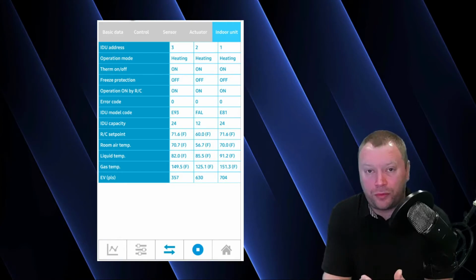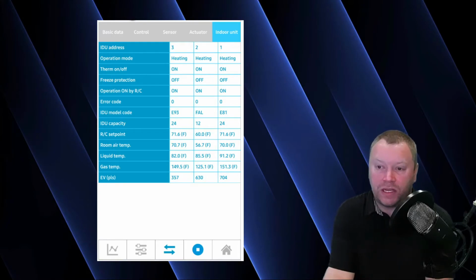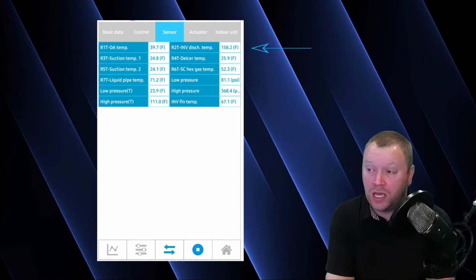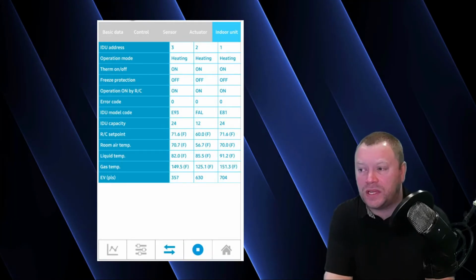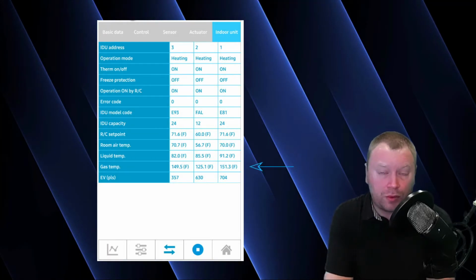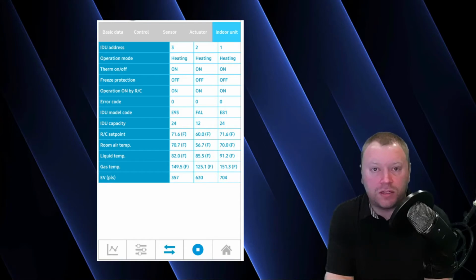We can continue through our refrigerant loop. So we have this hot gas. What was that temperature? Let's go back to our sensor tab and take a look at that temperature real quick. That was 158 degrees coming off of our compressor. And by the time we get to our indoor units, we have 149 degrees, 125 degrees, and 151 degrees. Your 2 2-ton units, unit number 3 and unit number 1, that show 150 degrees approximately, that entering gas temperature. Those units are fairly close to the outdoor unit. And that's why we don't see a lot of temperature change from the discharge of the compressor to our inlets of those coils. The wall mount, on the other hand, is a good distance away, a little over 100 feet, in fact. And so it is going to have a little bit more of a temperature drop by the time that hot gas gets to the indoor unit.